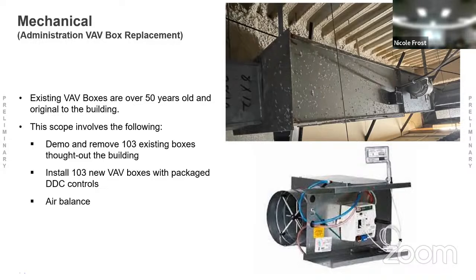So then this room will still have those same controls? No, these rooms will get all new controls - the whole building's getting completely redone, they just won't get boxes. Variable speed drives on the units are only for the units that have the boxes, because there's nothing to vary if it's just serving one space. Gotcha, it's all just direct up to the district.